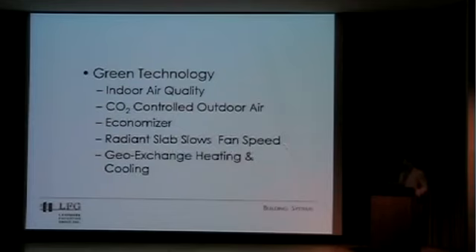This radiant slab that's installed allows us to run the main fan at a much, much slower speed than a normal building would. And it absorbs a lot of the heating load and a lot of the cooling load in the summertime, and it takes up most of the heating load in the wintertime. And reducing the fan speed increases energy efficiency and increases comfort because you don't have drafts blowing across occupants. And you also end up with the stratification, as I mentioned earlier, which allows multiple temperatures within the same building, and also reduces the energy costs.